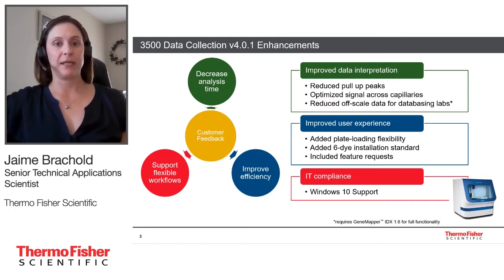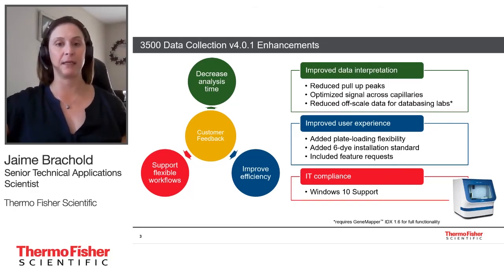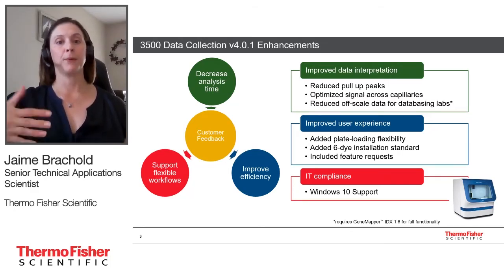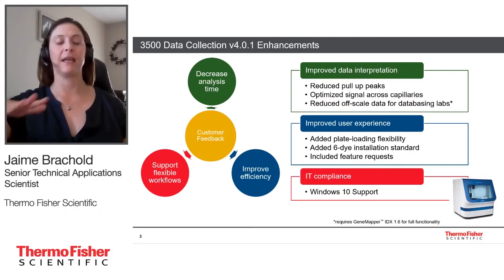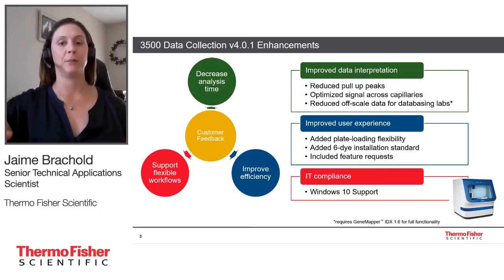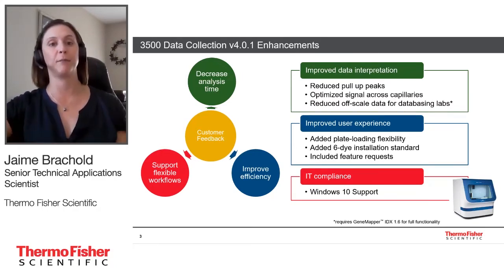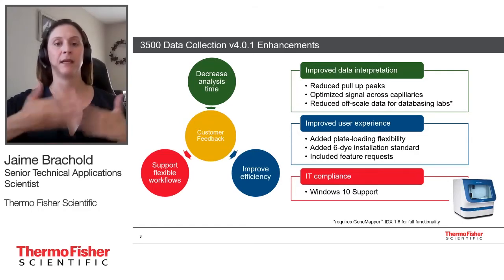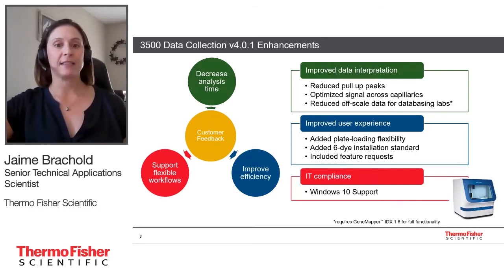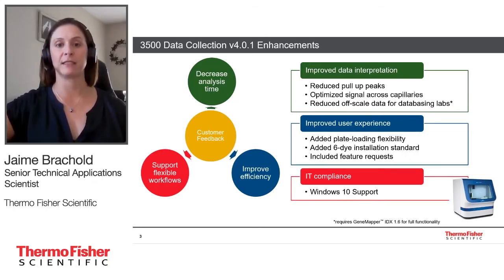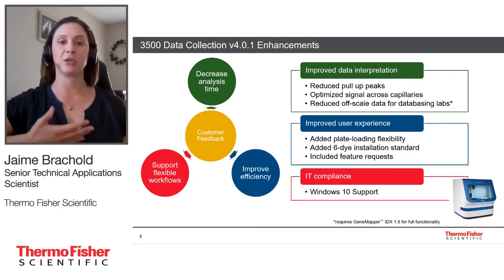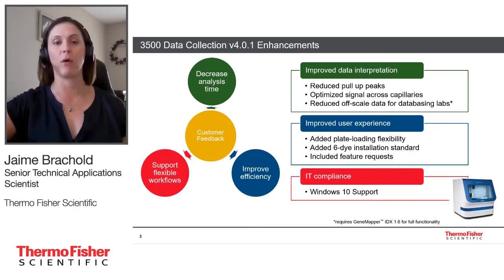We also aimed to improve the user experience, incorporating many feature requests. We added plate loading flexibility where you can pause a run, bring the auto-sampler forward, add a second plate, and restart the run. You can also pause a run after the first plate is completed, pull the auto-sampler forward, swap plates, and continue. We also added a 6-dye installation standard — on earlier versions, the HID performance check used Identifiler Ladder, but now you have the option to run a 5-dye with Identifiler Ladder or a new 6-dye with Global Filer Ladder performance check.